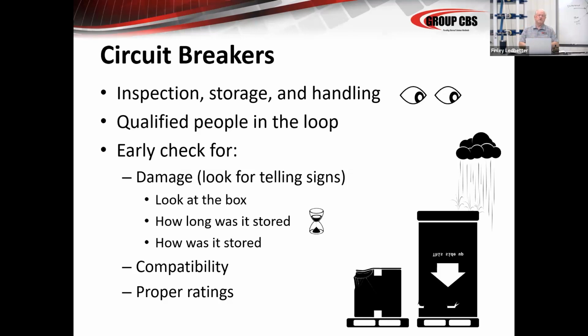Make sure the interlocks work, make sure all the secondaries line up and work, make sure everything works correctly, not only with the breaker, not only with the switchgear, but the combination of the two mating together. If they don't, you're going to have problems.